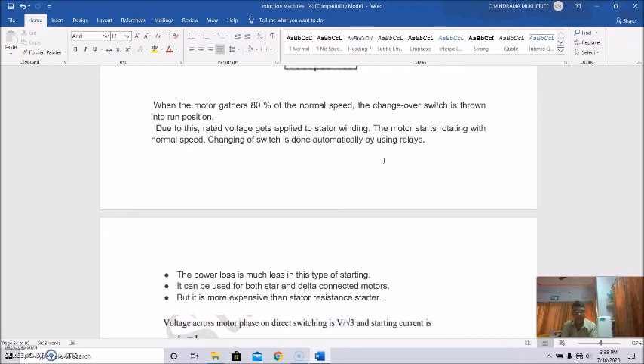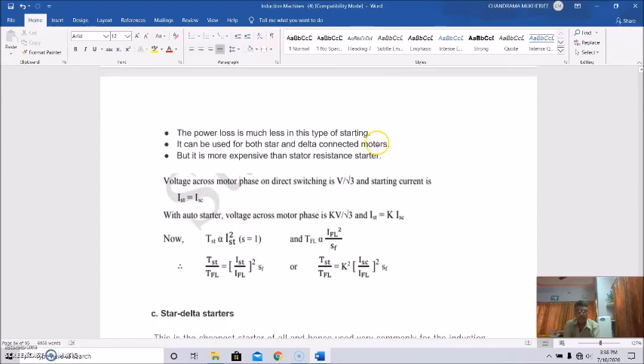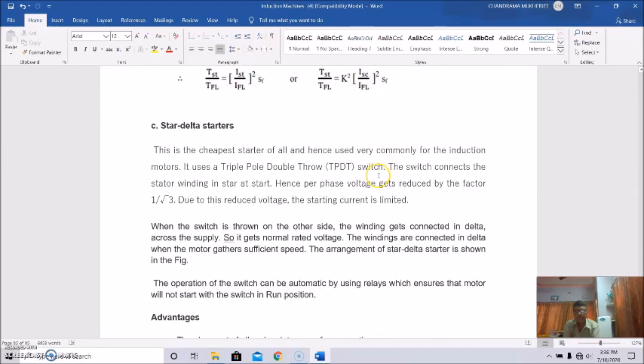It also ensures that when the auto transformer changeover switch is at the run position, the motor will not start. So basically, this is a protection, and that's why the cost is also high. And the cheapest one is the star delta starter we have discussed.